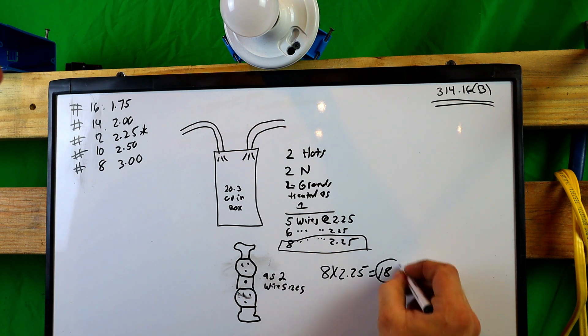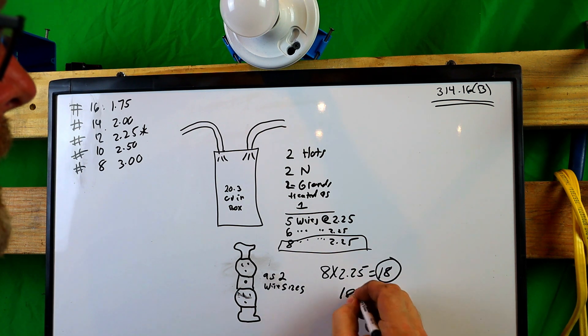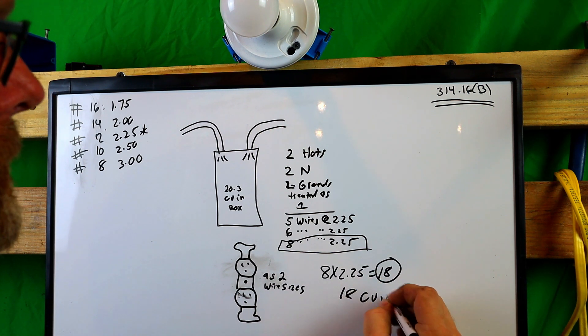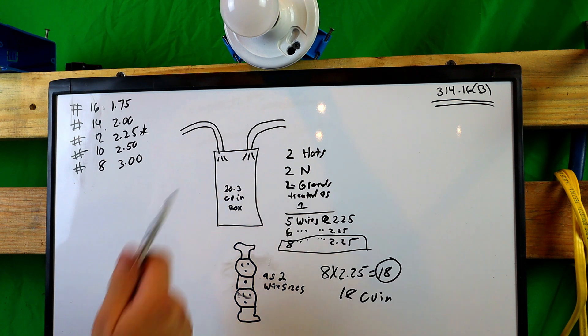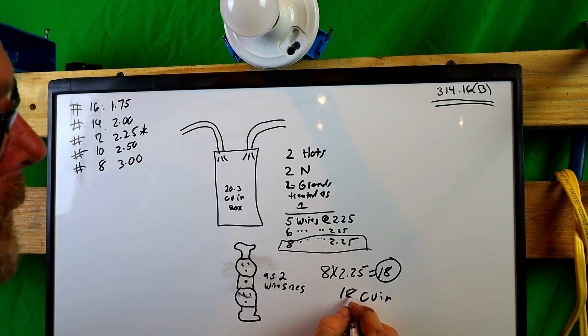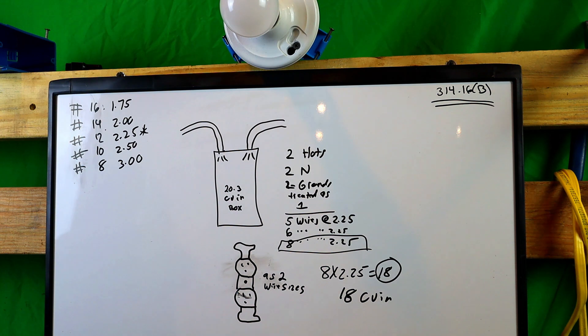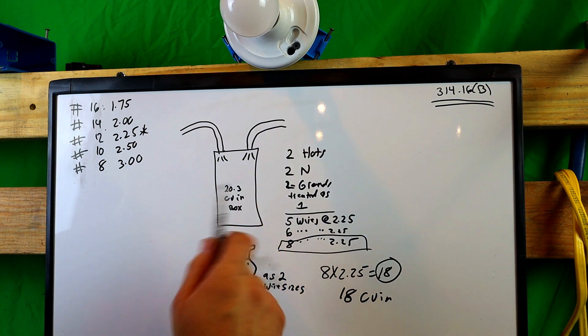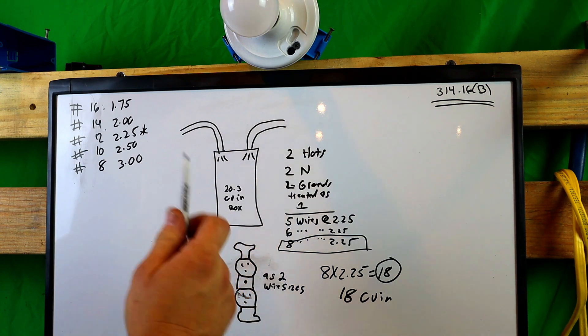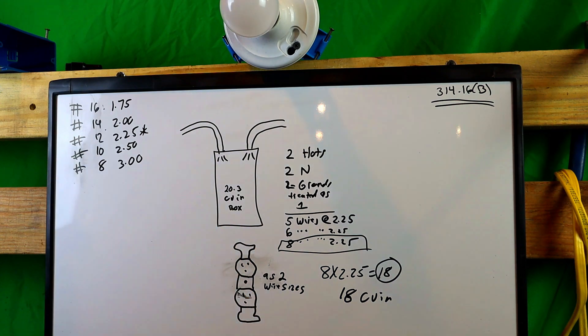So we have to do eight times 2.25 and that equals 18. So that's our number, 18 cubic inches. Now, this is how much this box will allow 20.3 cubic inches. And we have, well, that's a terrible, I'm a terrible writer also. Anyway, all this equals 18 cubic inches. So you definitely will have enough space.